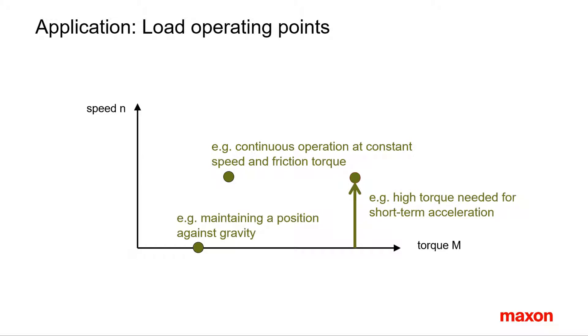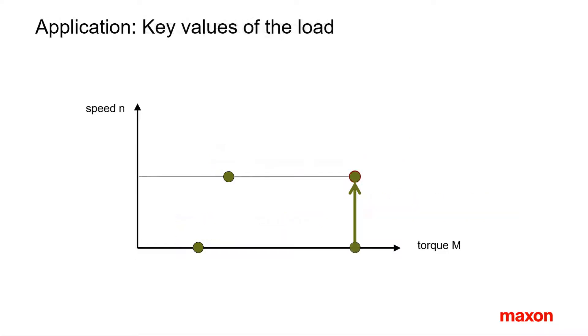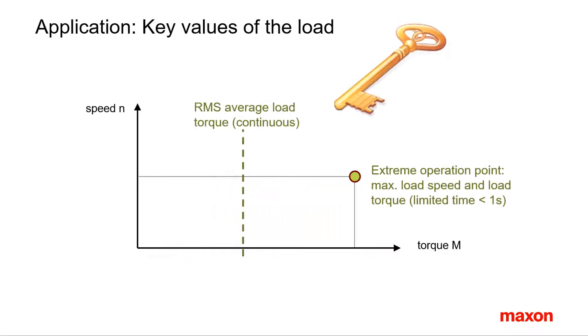The use of a gearhead is advisable if the speed is low, typically well below 1000 RPM, and the torque is relatively high. Regarding torque, we condense all the operation points into a few key values: the average RMS load torque and the extreme operation point, usually at the end of the acceleration where the maximum load speed and maximum load torque occur.